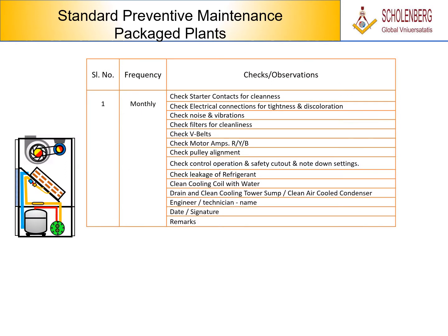Standard preventive maintenance, packaged plants. Serial number, frequency, checks, observations. 1. Monthly. Check starter contacts for cleanness. Check electrical connections for tightness and discoloration. Check noise and vibrations. Check filters for cleanliness. Check V-belts. Check motor amps, R, Y, B. Check pulley alignment. Check control operation and safety cutout and note down settings. Check leakage of refrigerant. Clean cooling coil with water. Drain and clean cooling tower sump, clean air-cooled condenser. Engineer, technician, name, date, signature. Remarks.